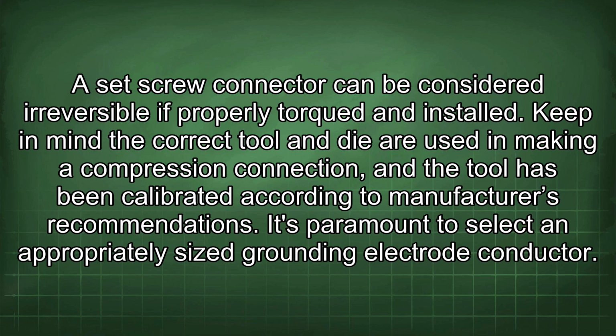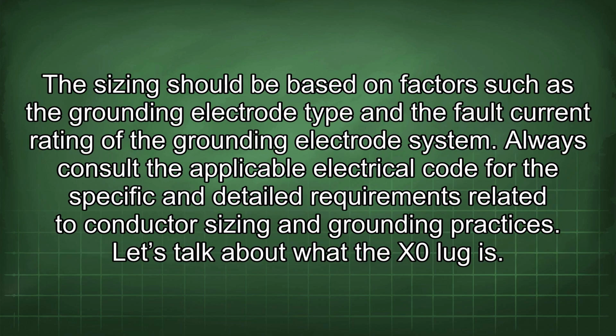Keep in mind the correct tool and die are used in making a compression connection, and the tool has been calibrated according to manufacturer's recommendations. It is paramount to select an appropriately sized grounding electrode conductor. The sizing should be based on factors such as the grounding electrode type and the fault current rating of the grounding electrode system. Always consult the applicable electrical code for the specific and detailed requirements related to conductor sizing and grounding practices.